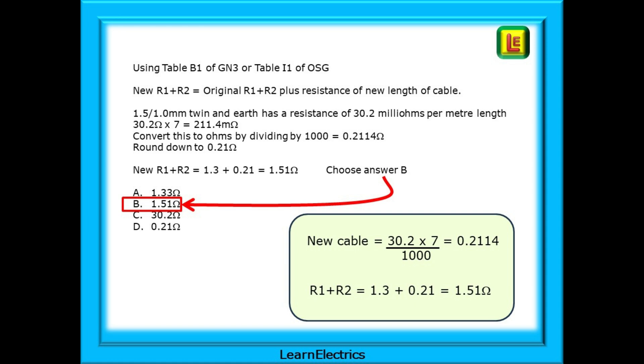The new R1 plus R2 will be equal to the original R1 plus R2, plus the resistance of the new length of cable. If 1.5 by 1 twin and earth has a resistance of 30.2 milliohms per meter length, then 30.2 milliohms multiplied by 7 is 211.4 milliohms. We can convert this to ohms by dividing by 1000 to give 0.2114 ohms, and then round down to 0.21 ohms.